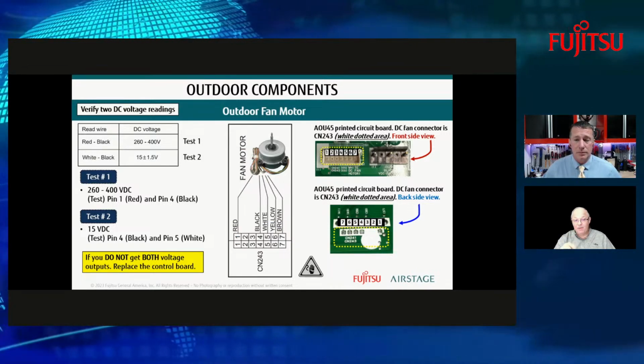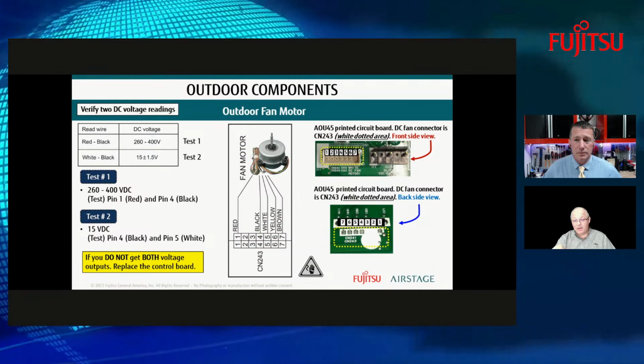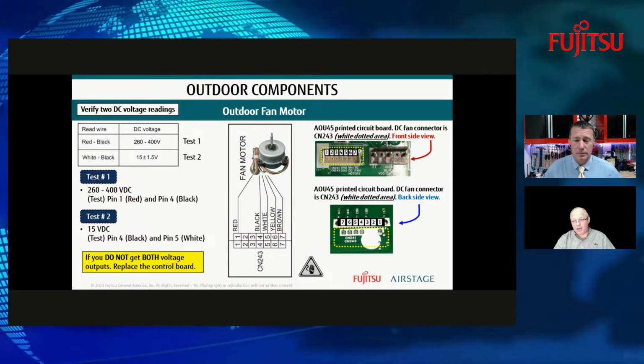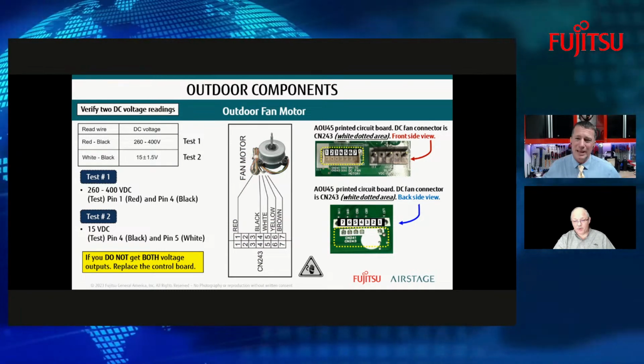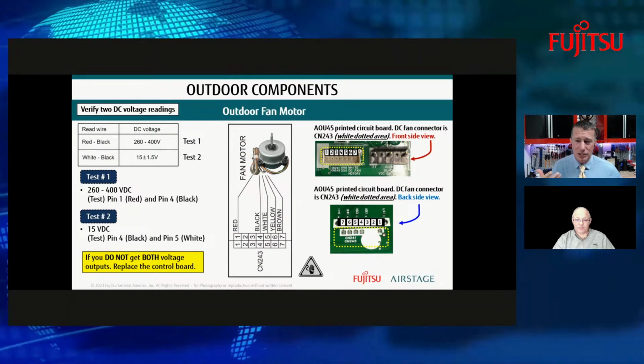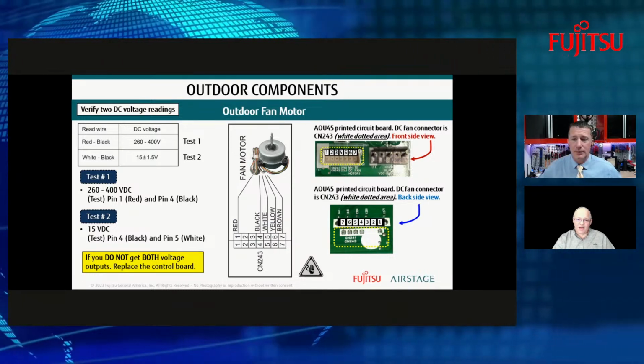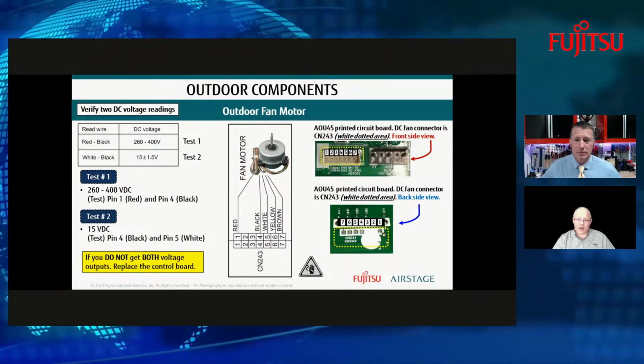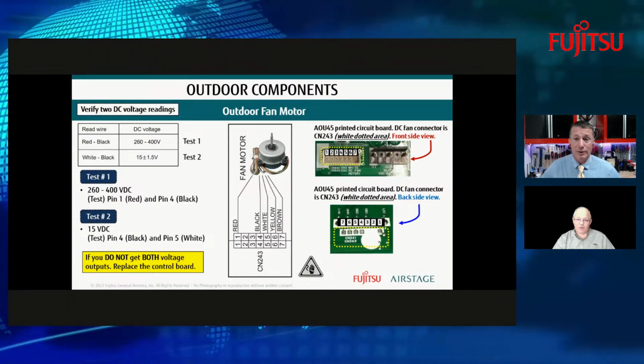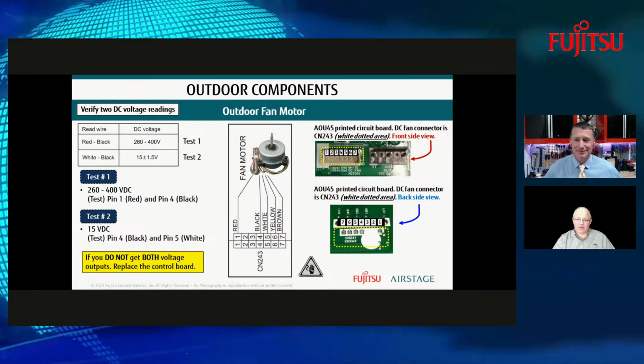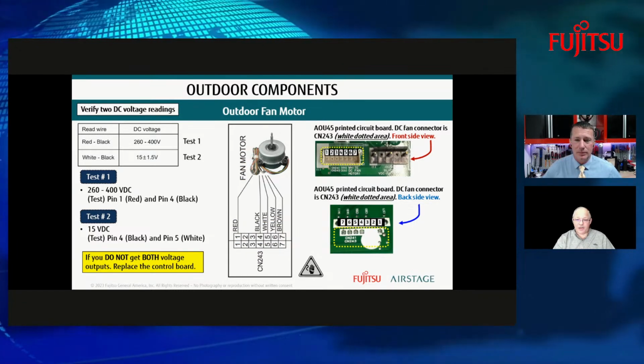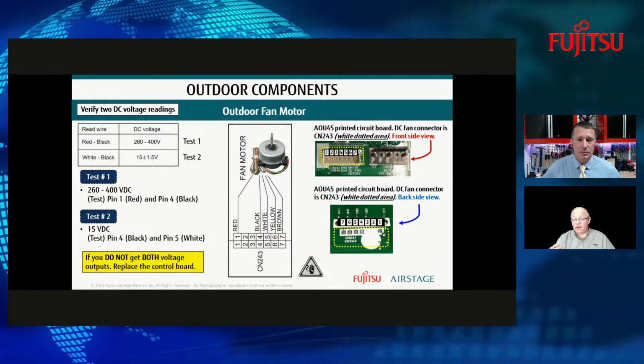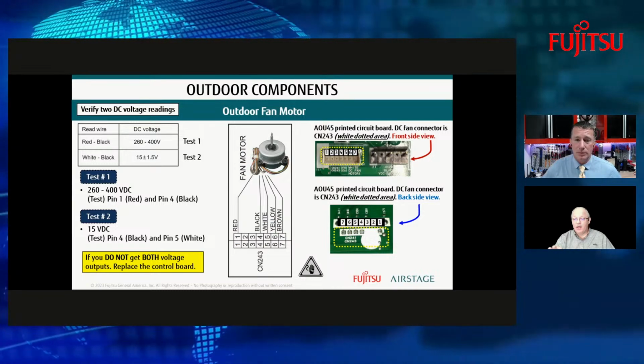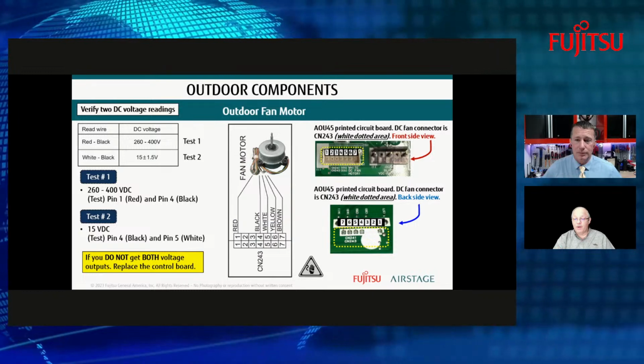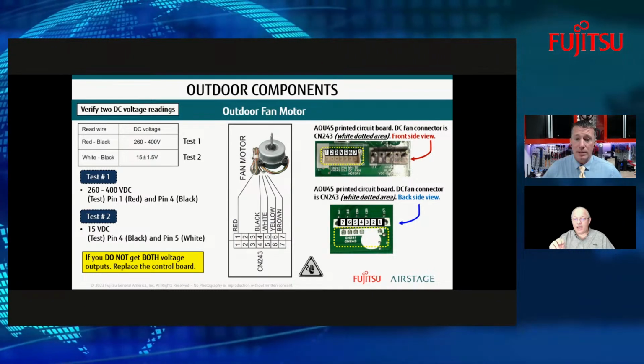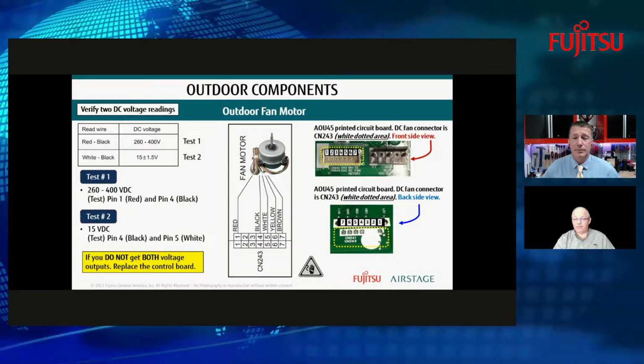Now, if you didn't have those readings, that wouldn't mean that the fan motor is bad outside. That means you may have a problem in the board itself. Now, would that be a time to disconnect the plugs to check voltage at all? Not generally. Most of the guys would probably check these right at the board itself, making sure that we're feeding from the board and then getting to the motor. Yeah, because it's up top and a lot easier to get to. And if you look at the picture in the upper right, you can see where it says DC fan motor, and it's got a little white imprint on it, so you know exactly which connector you're looking at. Okay. Fantastic.